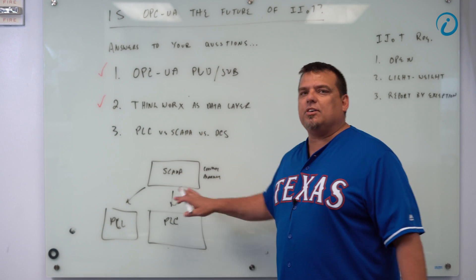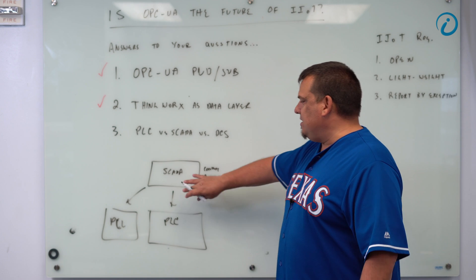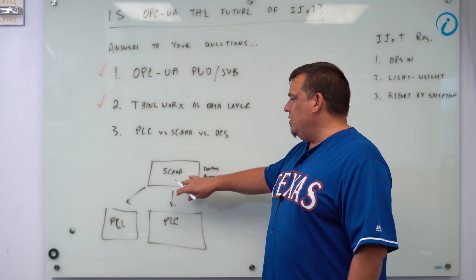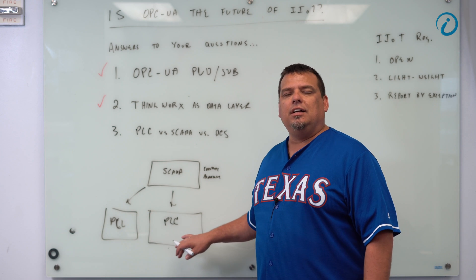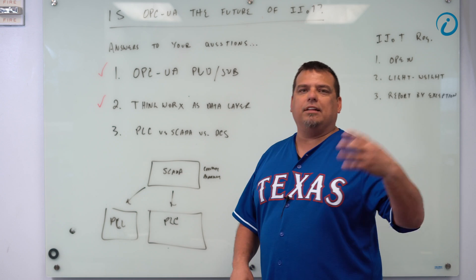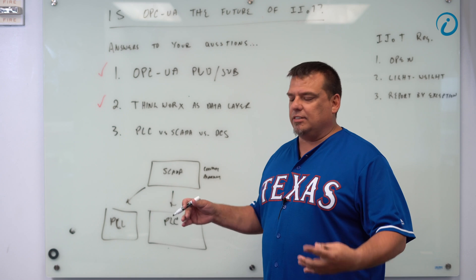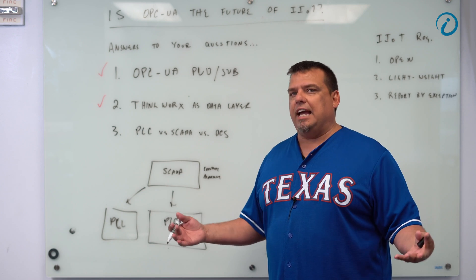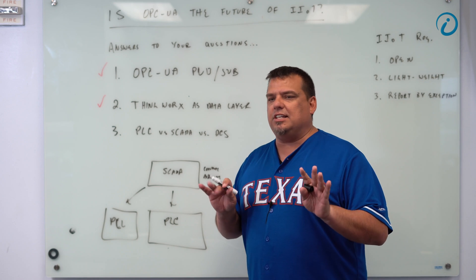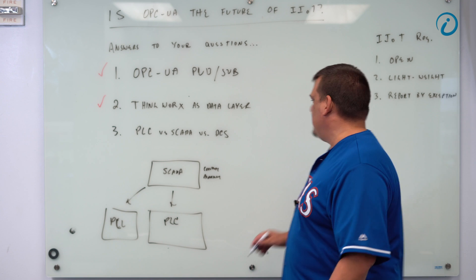DCS is very similar to SCADA but think of it as proprietary. My SCADA system if I buy an off-the-shelf piece of SCADA software, it generally doesn't care who the manufacturer of this hardware in the field is. It can talk to Allen Bradley, it can talk to Siemens, it can talk to Emerson, it can talk to anything. The SCADA software is generally open and it can talk to anything. A DCS system is generally, in most cases, it's process specific and it's all of this stuff turnkey process specific.